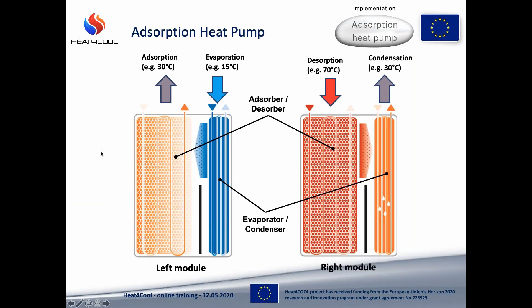First of all we have to replace the glass bulbs with heat exchangers. Then by circulating heat transfer fluid at different temperature levels through these heat exchangers we can warm up or cool down the sorbent, or we can supply or collect the heat from the water. Typically we use pure water as the heat transfer fluid due to its very good thermal properties, but I will use the acronym HTF to distinguish it easily from the refrigerant water.